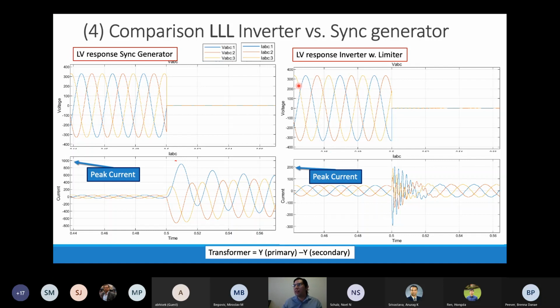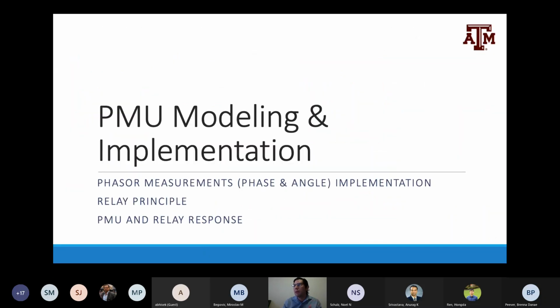And as you can see, the peak current is the critical factor here. Thanks to the limiters, we were able to reduce this current to what we defined, which was 1.2, in less than a cycle. This prevents further damage to the inverter, as I mentioned before, including thermal damage, and the semiconductors basically stopping functioning. So how do we model the PMU model in order to detect this type of fault?